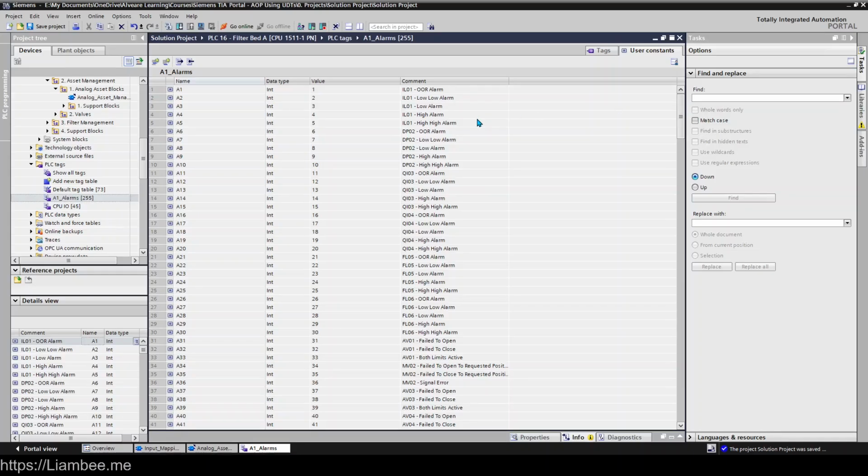And the nice thing about doing it this way is that you can allocate 255 alarms to a group. You can make it more if you want. In other projects, I've had 2048 and things like that. I try to keep them as nice programming numbers, just for size references. But you can allocate stuff and know that you can create new alarms, and all you're doing is dropping a function, because we should be making our alarm manager as a function.